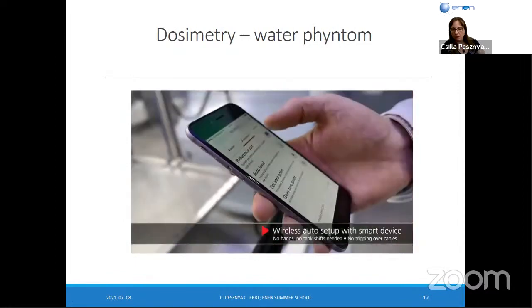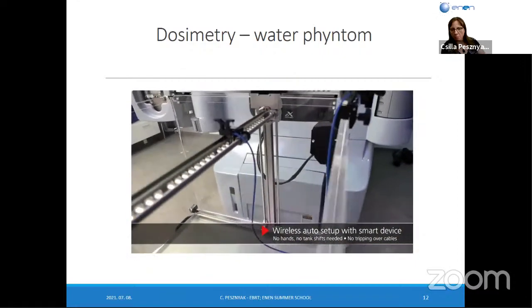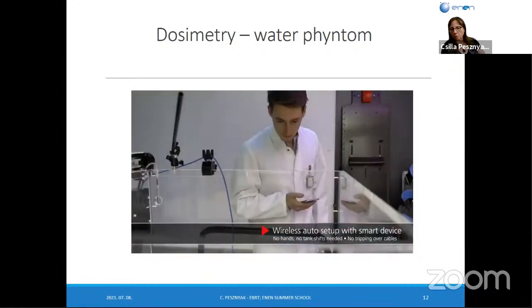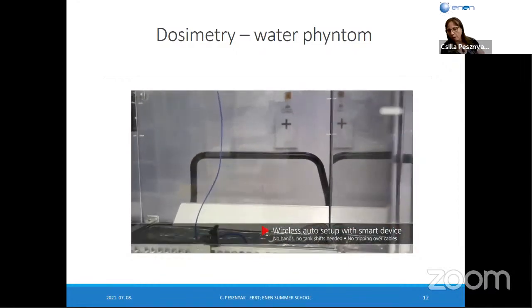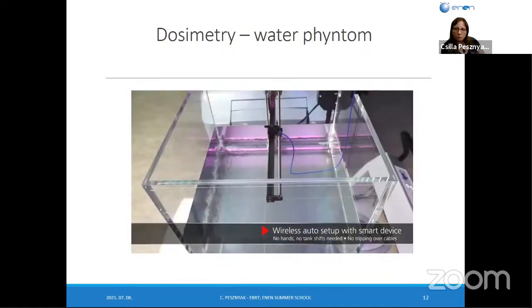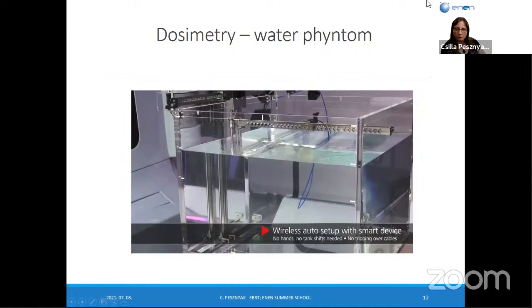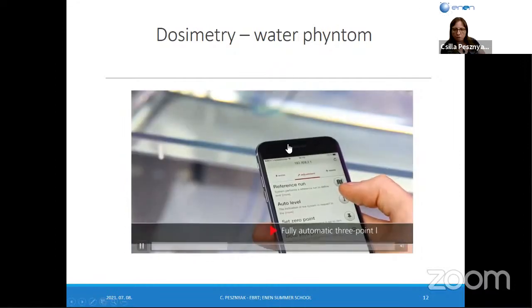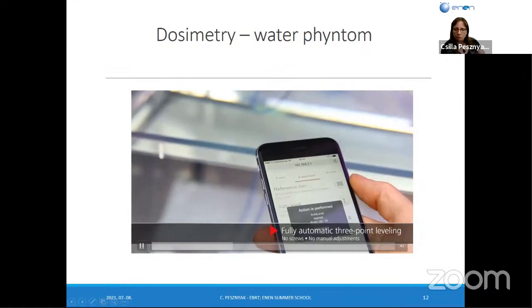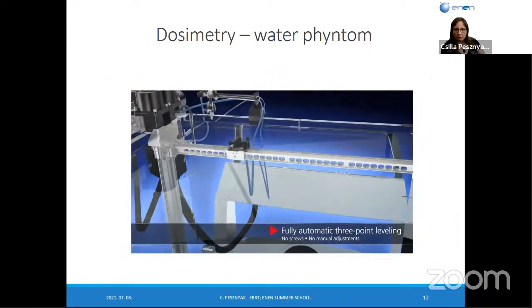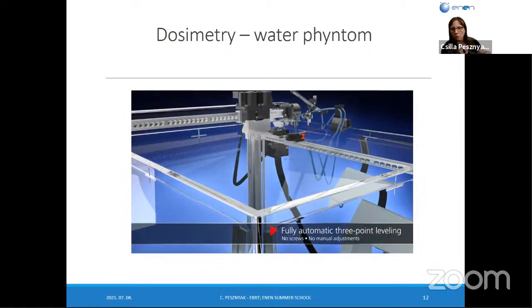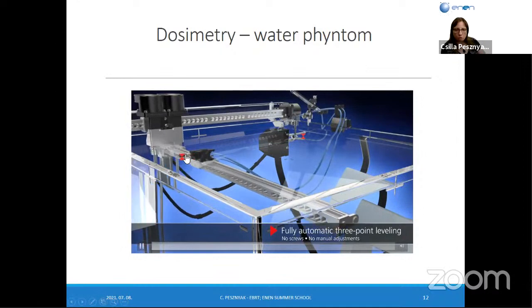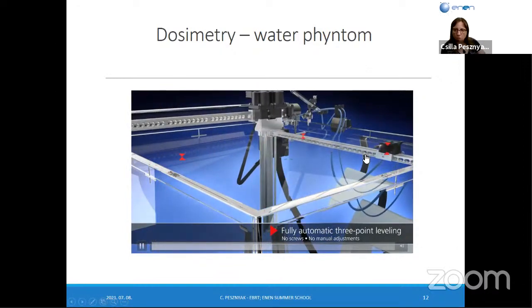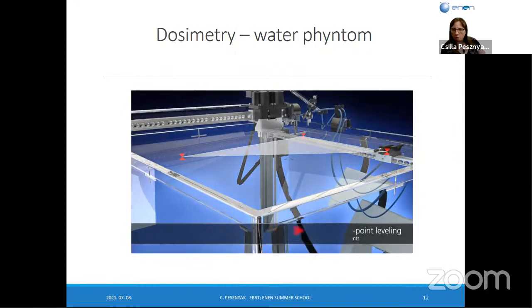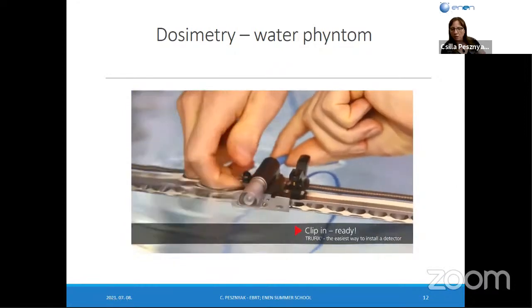You can use the wireless auto setup. These new water phantoms are very nice and work quickly. You can fill it with water, of course, and there is a special holder for ionization chambers. There is fully automatic 3-point leveling, and the chamber can move in all 3 directions. Here is the chamber. It is a semi-flexible chamber with very small dimensions, mostly used for photon beams.